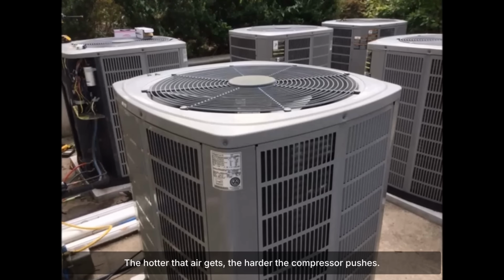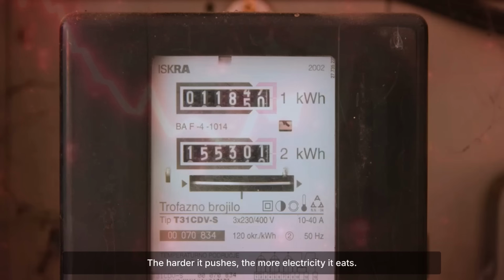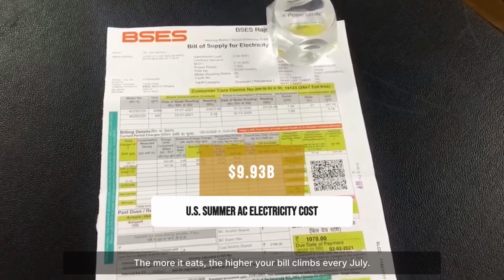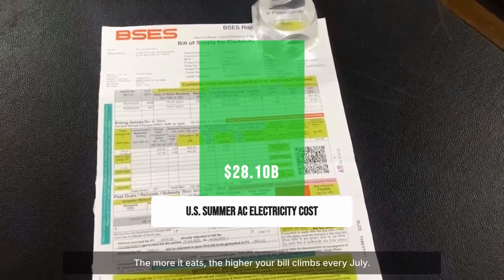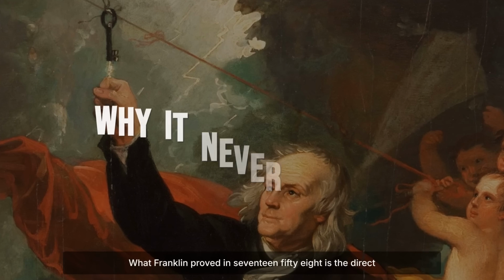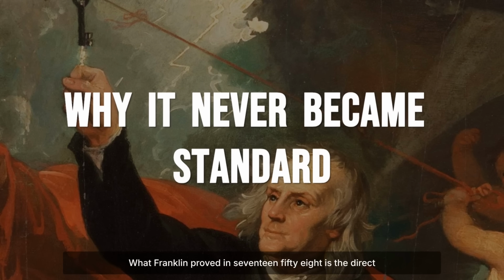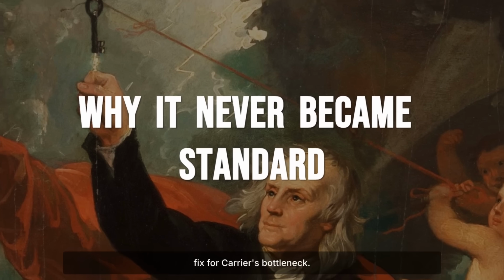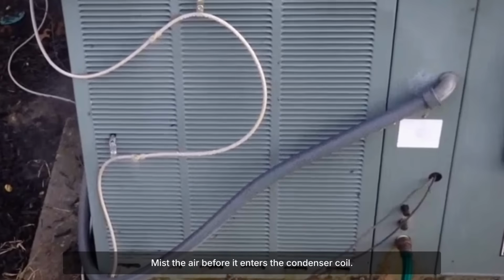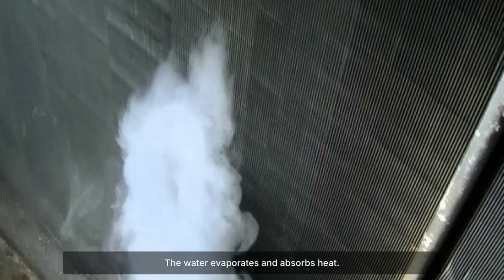The hotter that air gets, the harder the compressor pushes. The harder it pushes, the more electricity it eats. The more it eats, the higher your bill climbs every July. What Franklin proved in 1758 is the direct fix for Carrier's bottleneck. Mist the air before it enters the condenser coil. The water evaporates and absorbs heat.